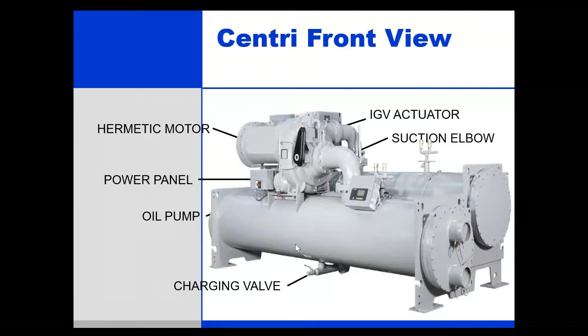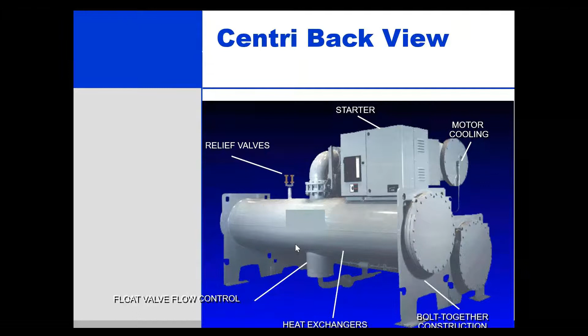This is the front view, and with that, I would also show the back view or the rear view of the centrifugal chiller, where you have a starter mounted, you have relief valves. In the semi-hermetic type of motor, you have a specific line which is called the motor cooling line, which you see on the right top. And of course, there's a float valve. You already had spoken about the float valve. The float valve is nothing but an expansion device which is used for the centrifugal chiller.